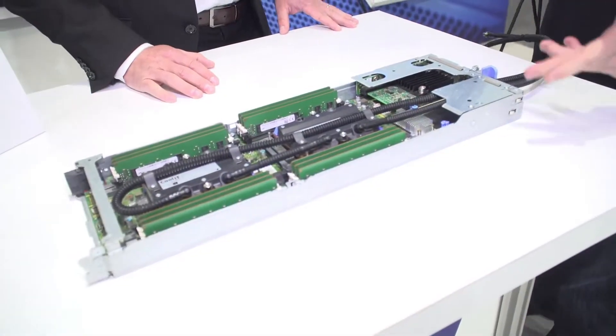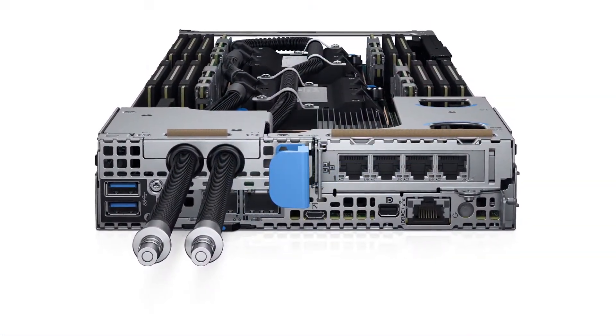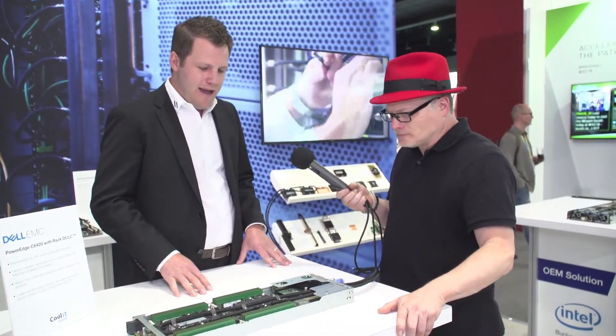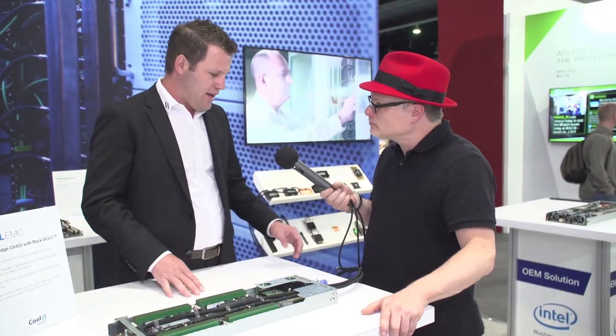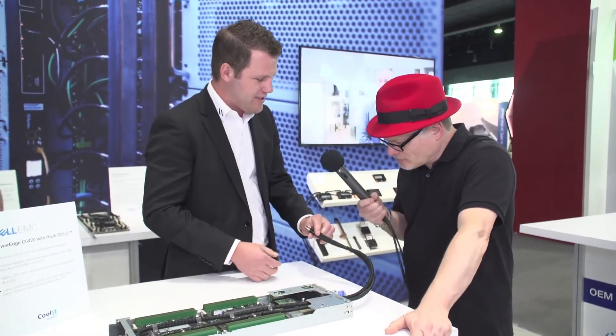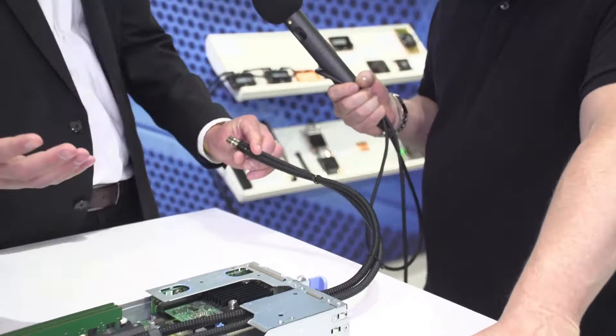What you're looking at is the Dell C6420 equipped with CoolIT's direct liquid cooling. In this configuration we're cooling the two Skylake CPUs. This manages about 65% of the total energy of the server into the liquid loop. It's a manual mating quick disconnect system, and this pairs with a CoolIT manifold and a CDU to complete the solution.